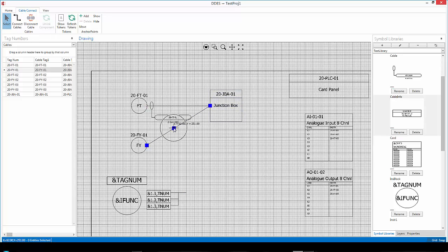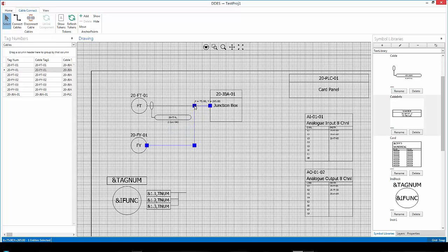If I were to go from the destination to the source, then, of course, my cable schedule will show that it goes from the junction box to the instrument. Remember, we work from the instrumentation all the way up to the card.